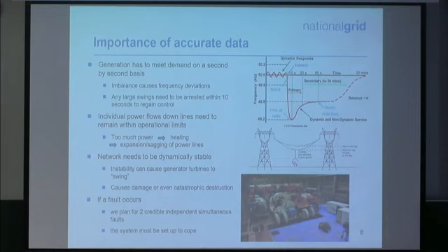If generation exceeds demand, then what happens is the big generators running find it too easy to operate. There's not enough resistance on the network. They spin too fast, and there is a tolerance. They're supposed to spin at 50 hertz. If they spin at more than 50.5, they'll start to shake and rattle. Round about 52, they'll probably come off their bearings.